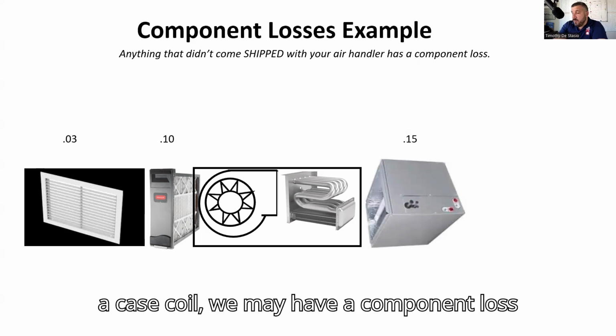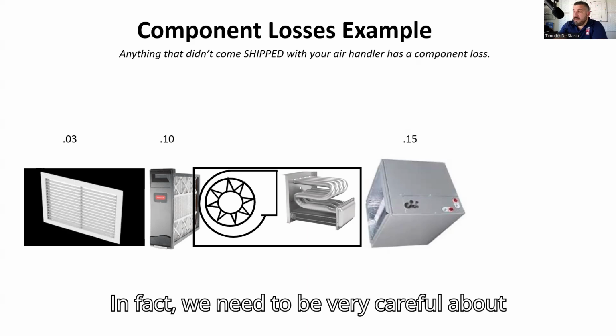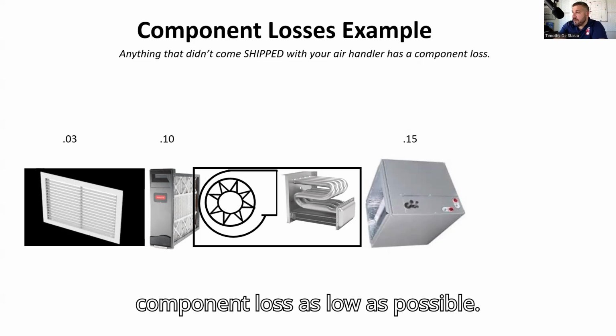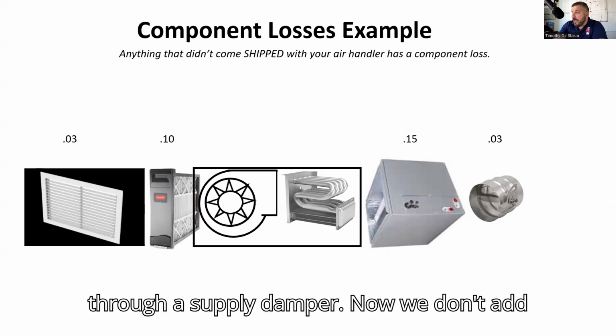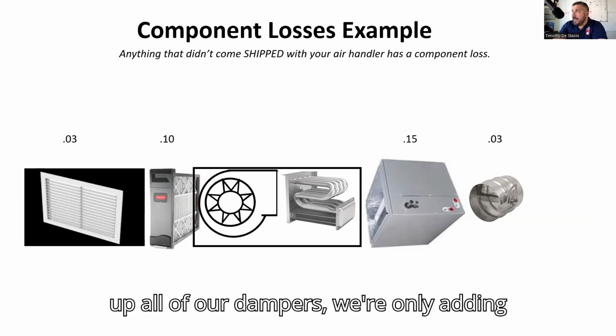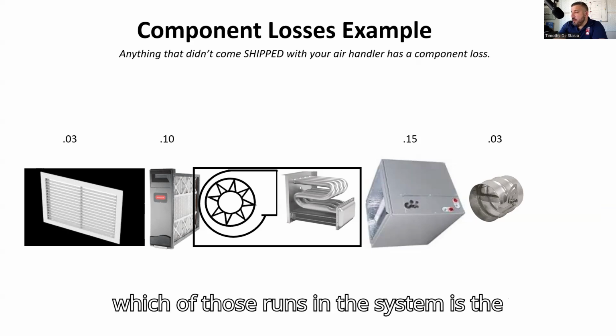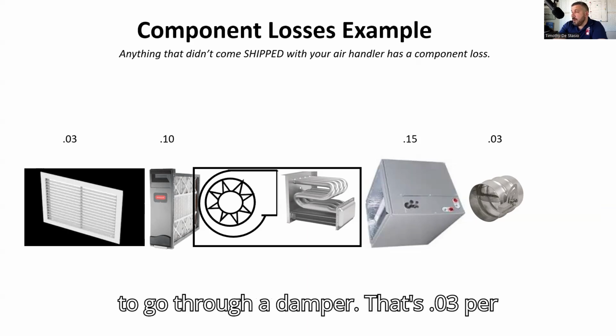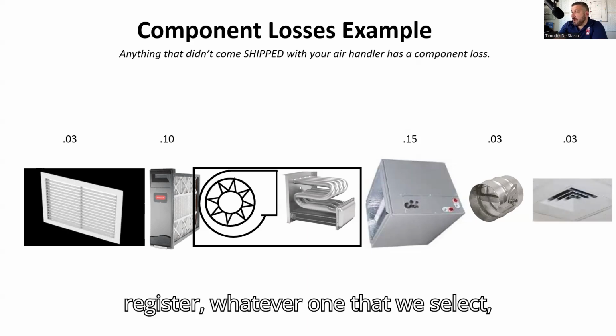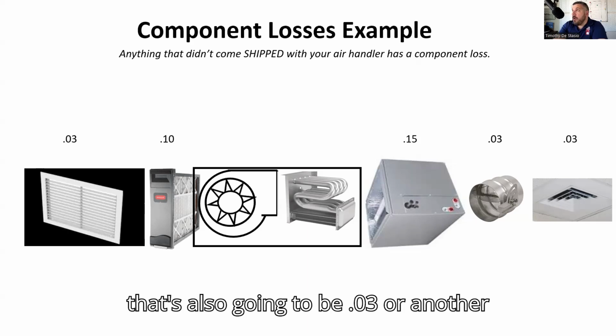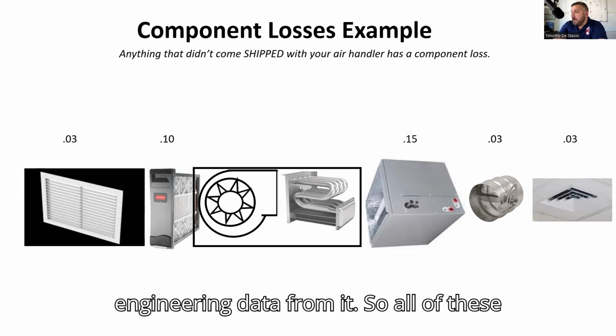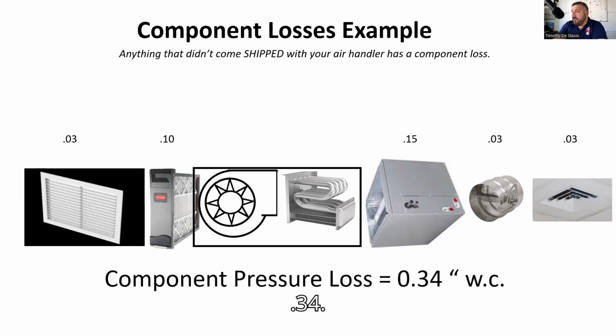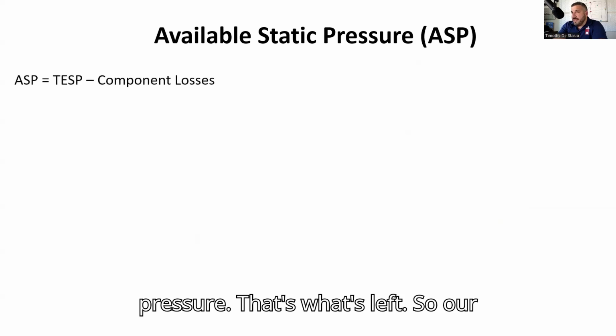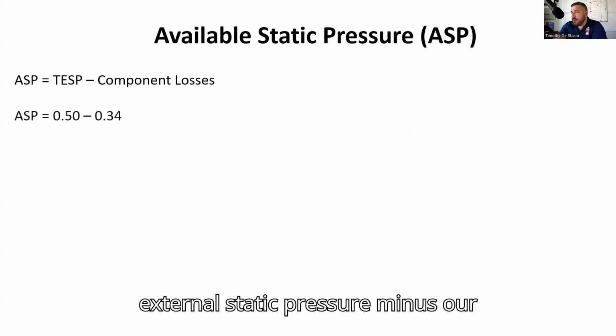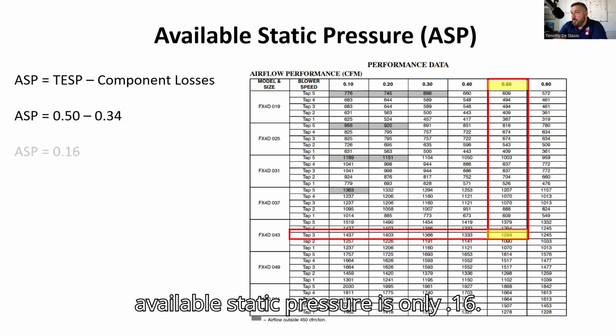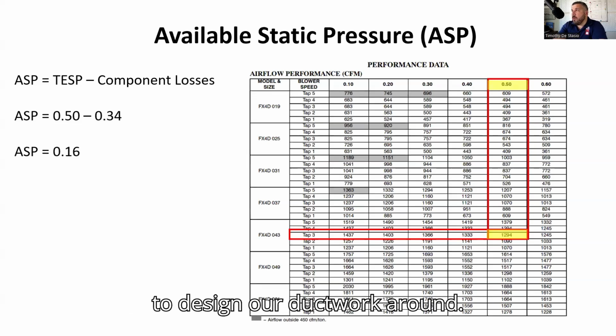Then on the supply side, if we have a case coil, we may have a component loss anywhere around 0.15 or even higher. In fact, we need to be very careful about what coil we select to try to keep that component loss as low as possible. And the air is going to always pass through a supply damper. Now, we don't add up all of our dampers. We're only adding up one damper because we're looking at the longest run here. And so no matter which of those runs in the system is the longest run, they're always going to have to go through a damper. That's 0.03 per Manual D. And then finally, the supply register, whatever one that we select, that's also going to be 0.03 or another number if we have that number from the engineering data from it. So all of these components add up together to 0.34. And that leads us to our available static pressure. That's what's left. So our available static pressure is our total external static pressure minus our component losses. In this case, our available static pressure is only 0.16. That is the static pressure that we have to design our ductwork around.